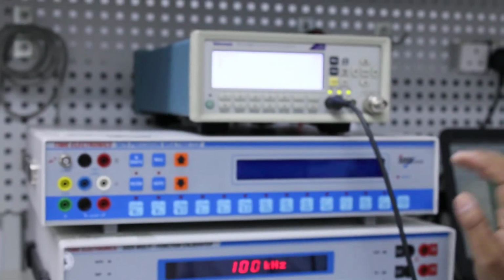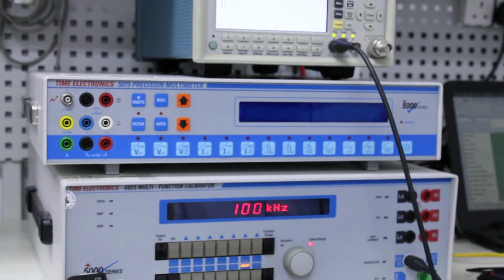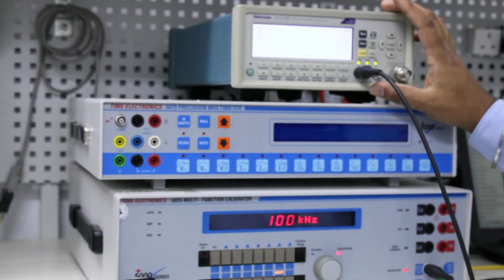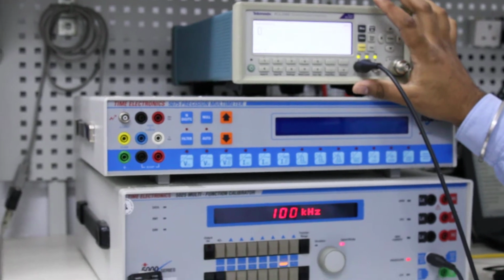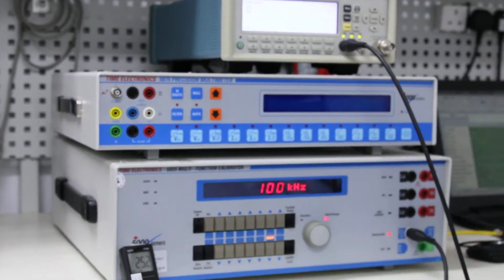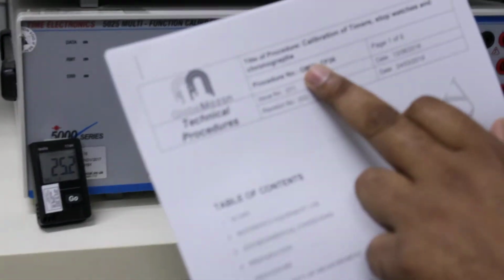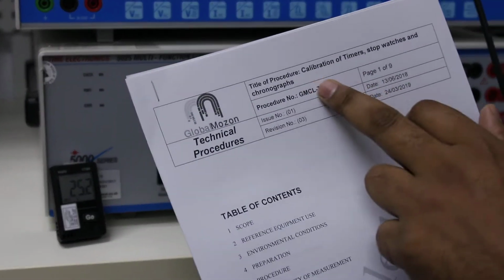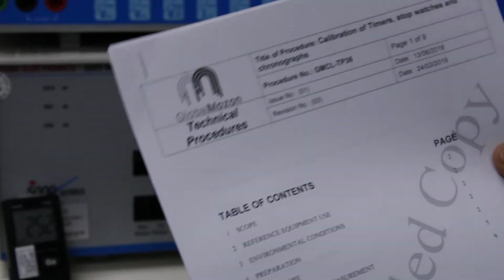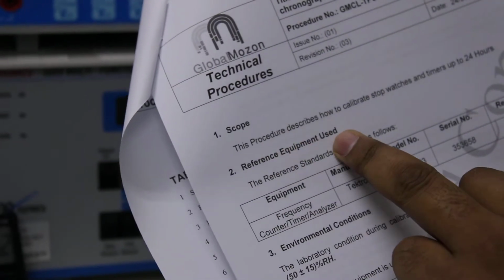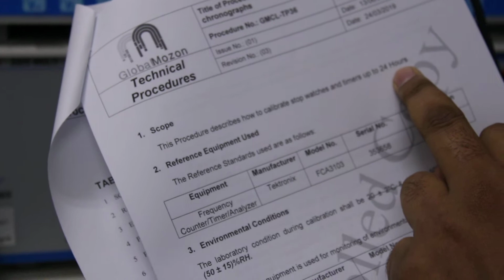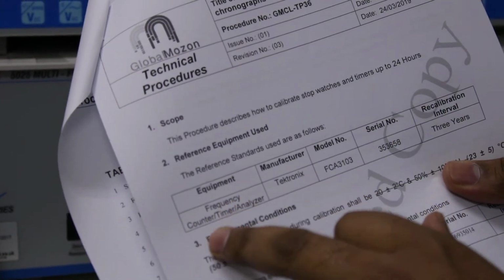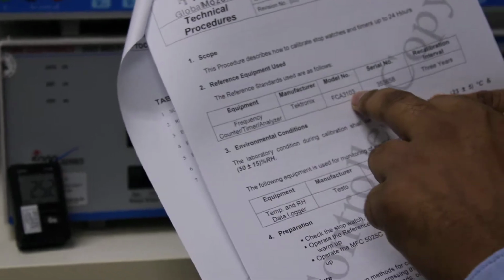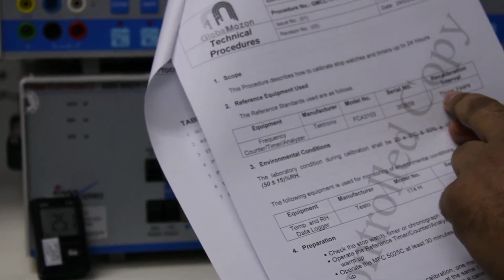212Q03R. For this calibration we have used our multifunction calibrator for the frequency test, and we have connected our frequency cable to this Tektronix FCA3103 timer counter analyzer. For this calibration we are using the procedure titled Calibration of Timers, Stopwatches and Chronographs, GMCL-TP36. This procedure describes how to calibrate stopwatches and timers up to 24 hours. We are using reference equipment, the frequency counter and time analyzer Tektronix FCA3103, with serial number 353658, three-year calibration.